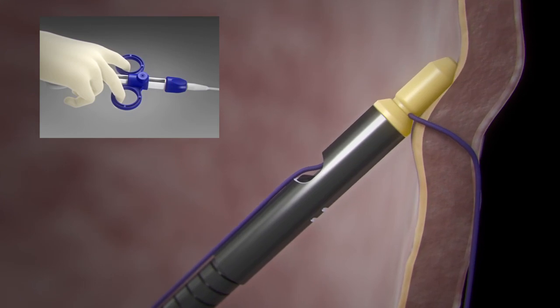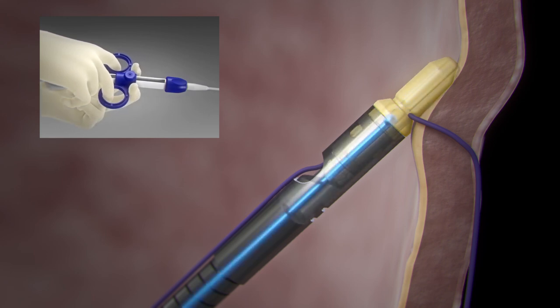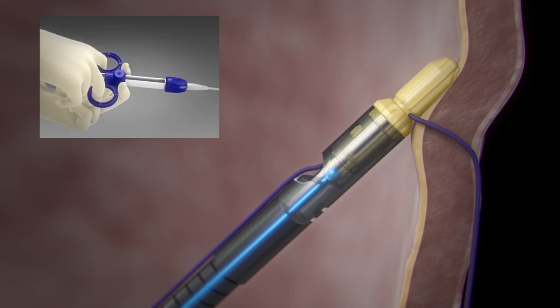Stage 2 of deploying the cinch will require two hands. Continue to squeeze the cinch handle to advance the beaded rod through the PEEK plug.